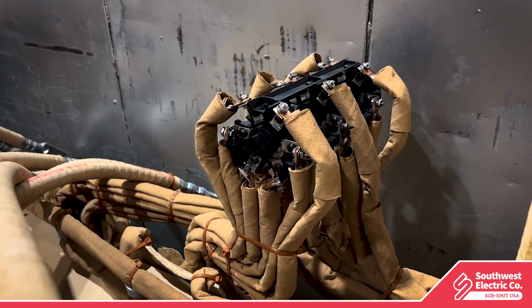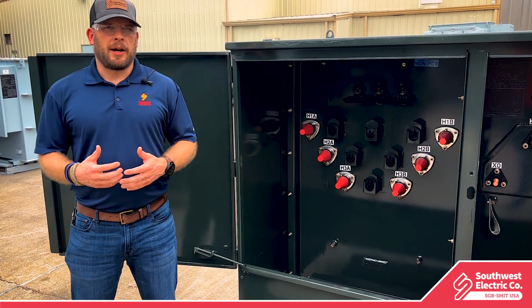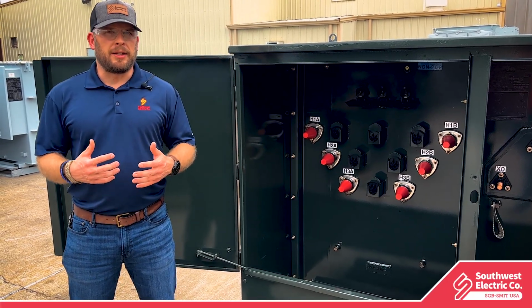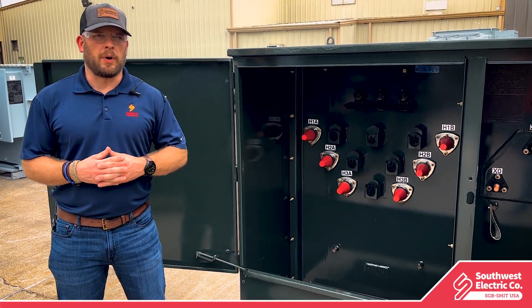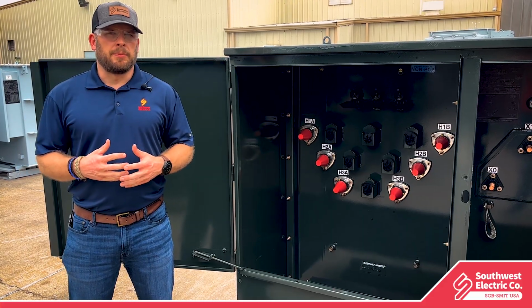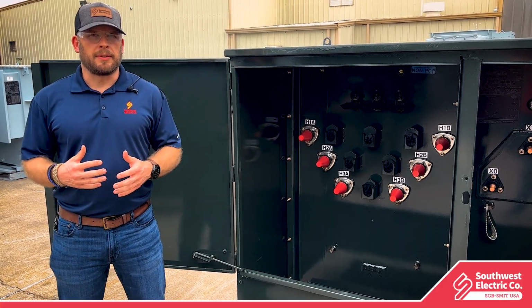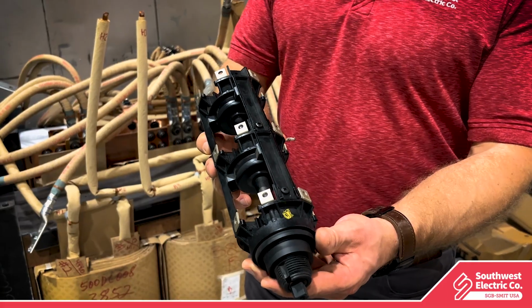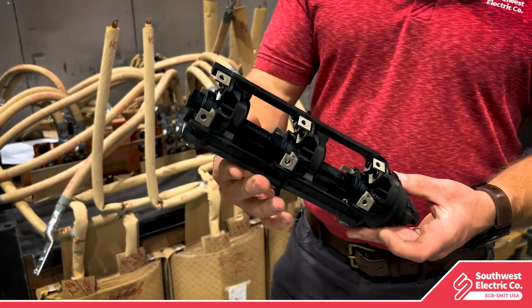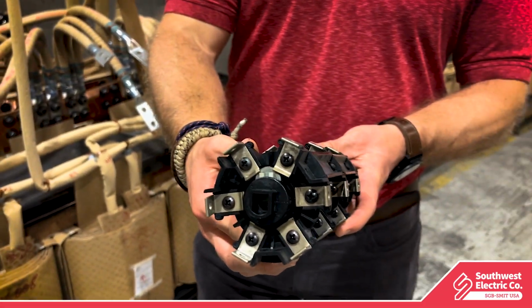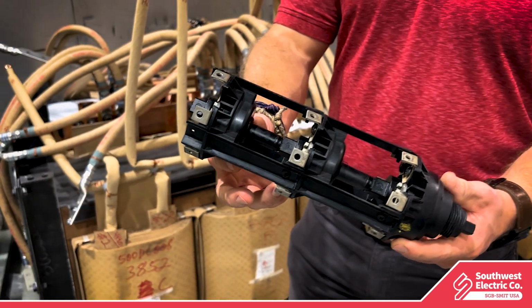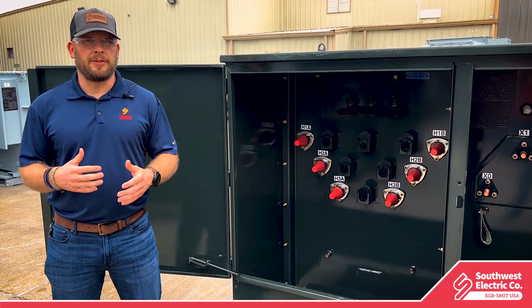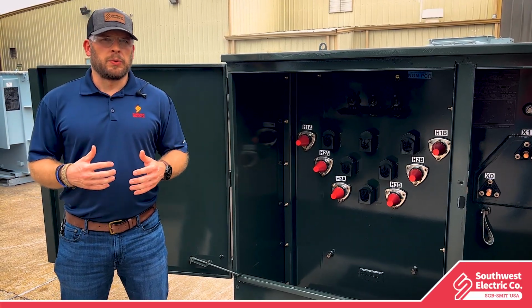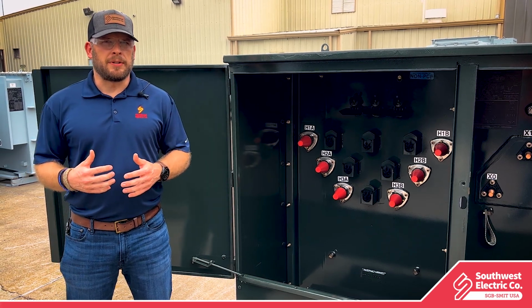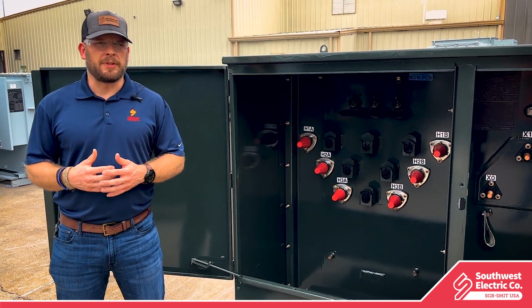So, how do they work? The way that tap changers allow us to regulate the output voltage is by changing the number of active turns in the winding. The physical connection points on the transformer windings are referred to as taps and represent different coil turn counts. When you change the tap, you are altering the winding ratio between the primary and secondary windings, which will in turn change the output voltage. This will allow you to either increase or decrease the voltage depending on the needs of your system.